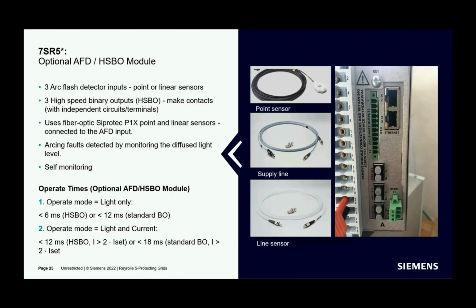Now, an important part of 7SR5 to complete the protection application. The 7SR5 devices have the option for direct arc flash detection inputs, with high-speed tripping open contacts for fast clearance when an arc fault is detected in the enclosed switchgear. So this is optional hardware, but again, you don't choose any functionality, you just add the hardware module at the beginning, of course.